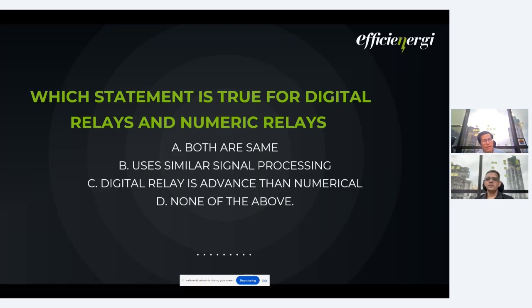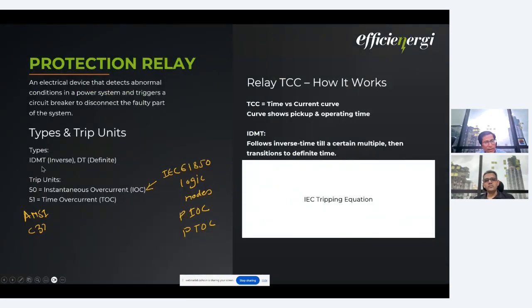Okay, again, these are the constructional aspects of the relay that we are not going to talk about today. We are going to talk about the tripping characteristics of the relay. We always hear IDMT and DT. IDMT is inverse definite minimum time curves, and there are definite time curves. We always see these tags given by ANSI standards, 50 and 51. But now, as we are using the communication protocol as per IEC 61850, it has logic nodes denoted by PIOC and PTOC. IOC means instantaneous overcurrent, and TOC means time overcurrent.